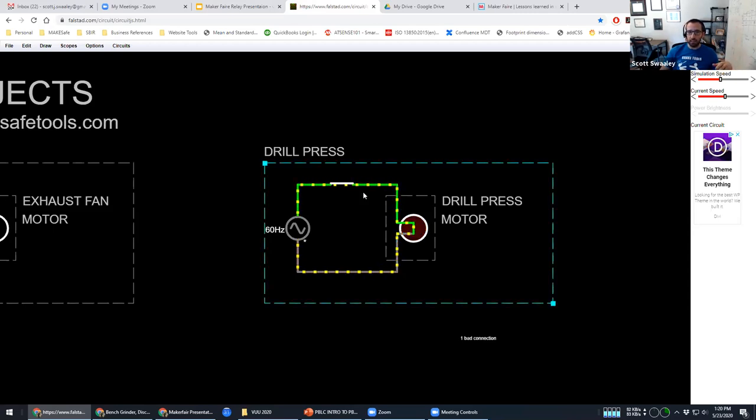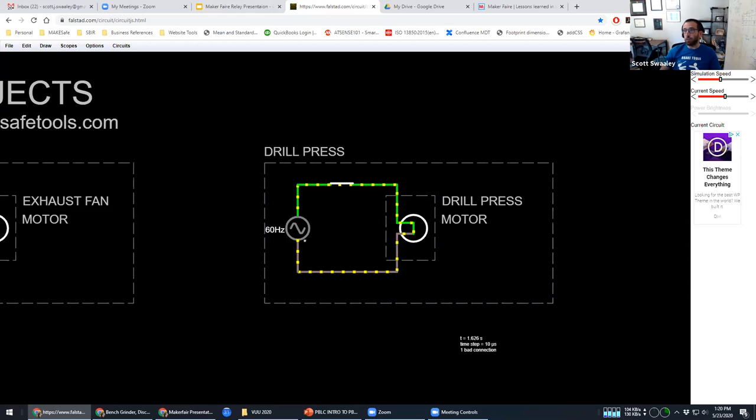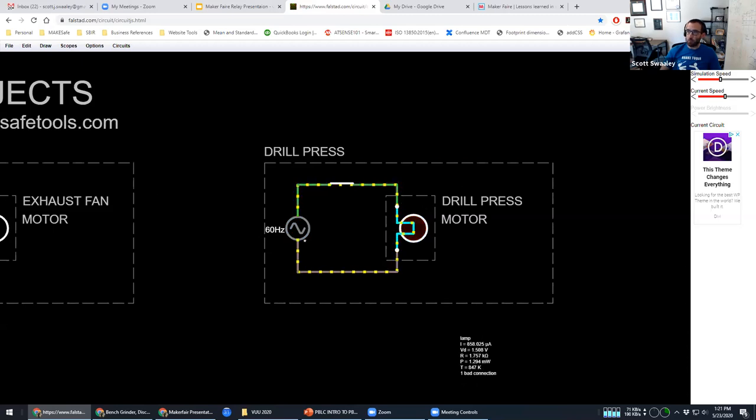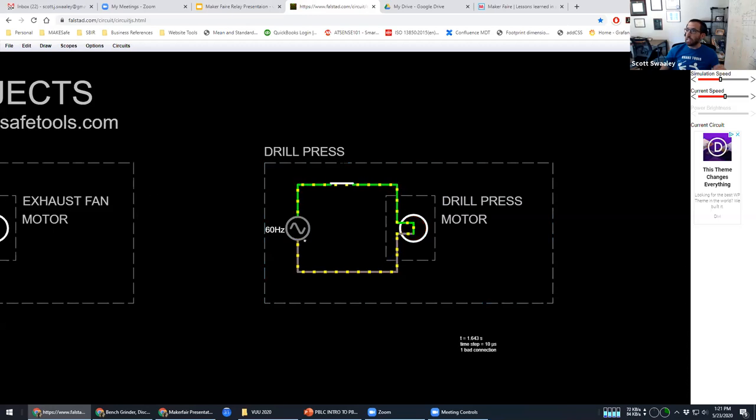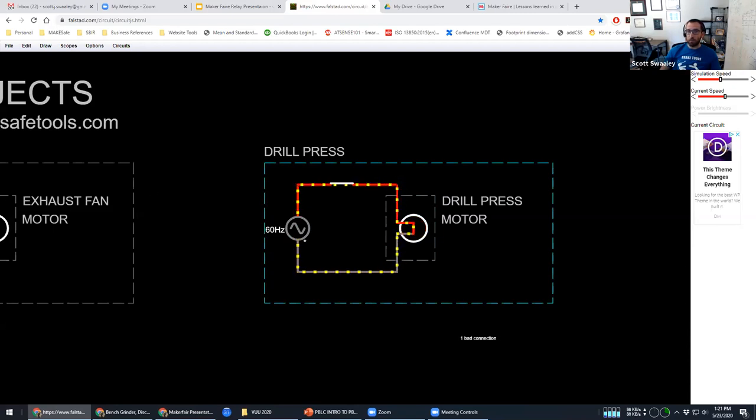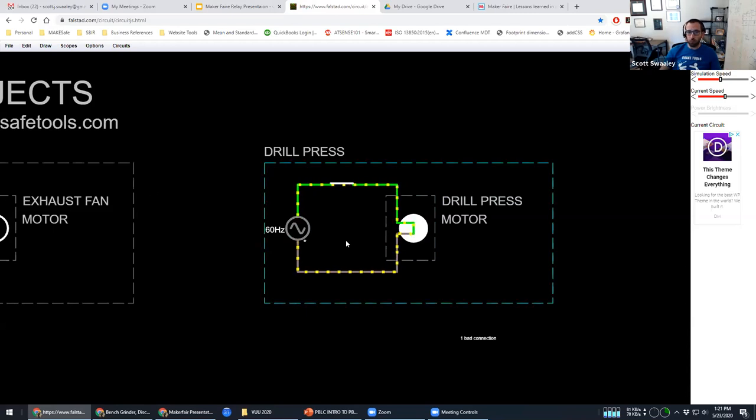Or let's say that when you're rolling the saw outside, right? It's obviously unplugged, right? You're rolling it outside. And while you're rolling it, someone accidentally presses that switch, whatever. And then while somebody is setting up their work, somebody plugs it in. Guess what? Your band saw just turned on and someone's hands were probably not where they should be. So this is actually called an accidental restart. This is something that in the industrial world is actually regulated to not be possible. Now it doesn't mean people do that, but it is actually legally required in any workplace that any machinery cannot automatically restart itself. And so that is kind of scary because the way tools come even brand new is they will naturally do this. They will naturally start themselves up and put everyone at risk. And so there's a way we can solve this with relays.